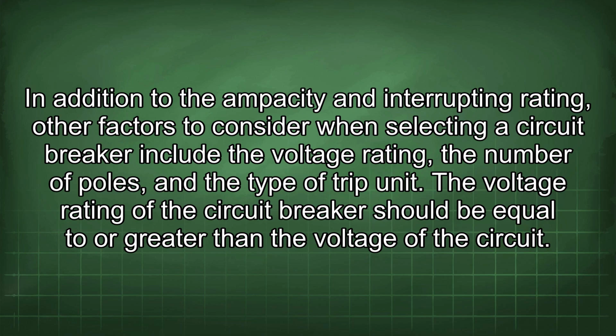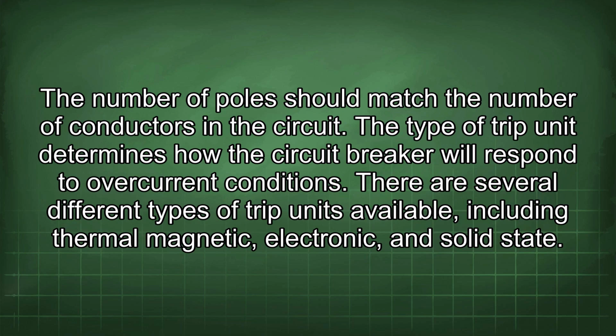The voltage rating of the circuit breaker should be equal to or greater than the voltage of the circuit. The number of poles should match the number of conductors in the circuit. The type of trip unit determines how the circuit breaker will respond to overcurrent conditions. There are several different types of trip units available, including thermal, magnetic, electronic, and solid state.